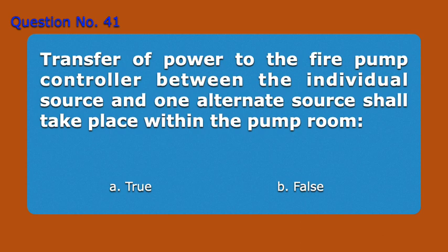Question number 41. Transfer of power to the fire pump controller, between the individual source and one alternate source, shall take place within the pump room. A. True. B. False. Answer A. True.